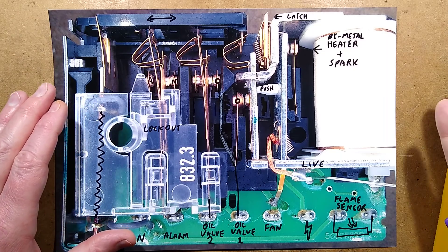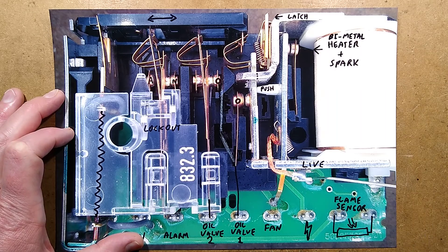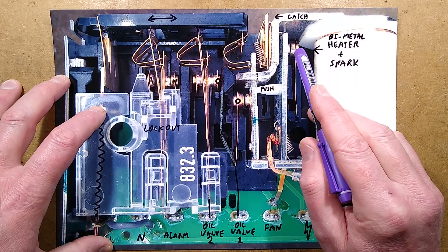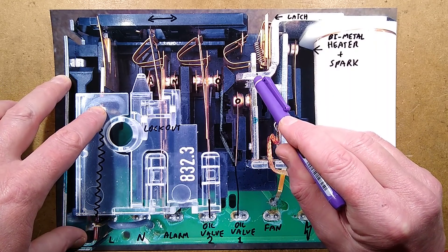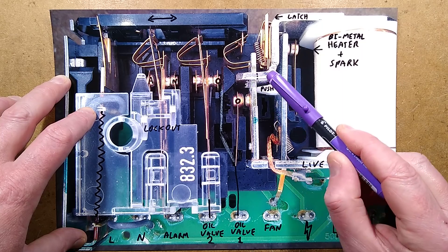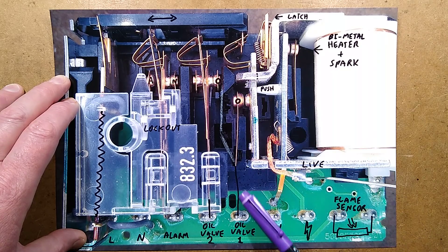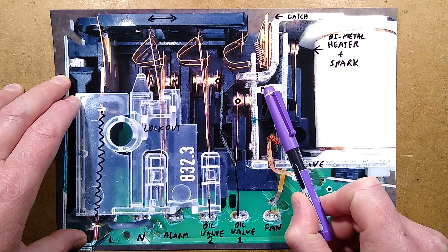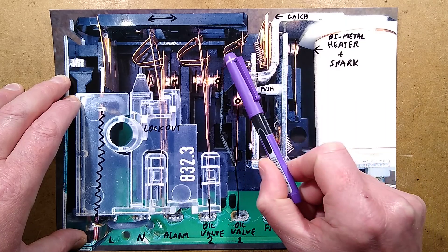That means it's possibly sensing a light in the room which would indicate that flame was there. So when that happens, it would not give an indication of whether proper ignition occurred. So what happens there is it goes through the normal sequence. But because this is powered all the time, this coil here, it has a magnetic field. And if you see, I've added a few dots here. The magnetic field that, because it's happened out of sequence, this plate here is now held magnetically. And because it's held magnetically, the thing is going to traverse up but it's not going to be able to flick that switch. So the oil valve is not going to light. This is not going to be able to break because this little plunger here is stopping that from going forwards, because that's already held magnetically and didn't click over out of the way. And the thing then stalls at the end and then trips the lockout.